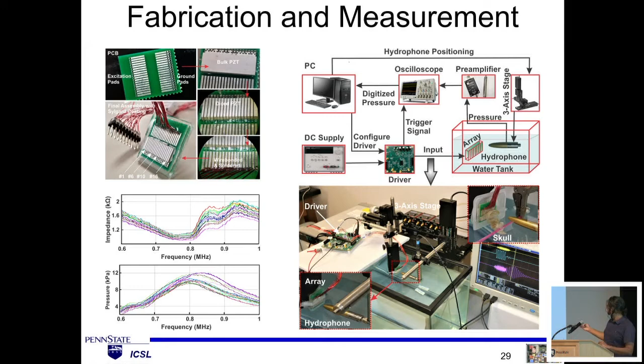And then we characterize the electrical impedance for each of the elements, and also the pressure generated by each of the elements. So then, time for the measurement. This is the measurement setup. That is an automated setup. It can scan 2D or 3D fields, whatever you want. And it's totally automated.